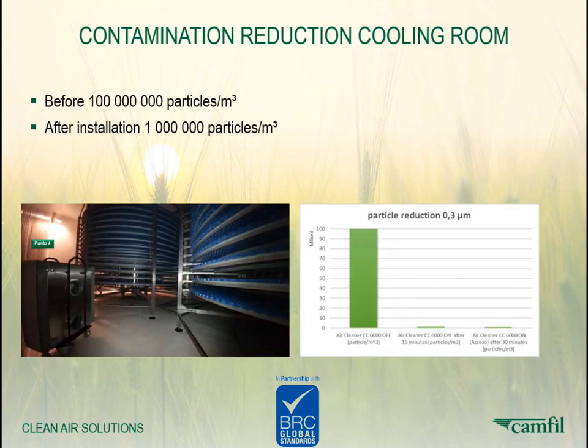With this slide, we'll describe the reduction of particles in the cooling room. In the staple diagram, you see the high green staple before installation with a concentration of 100 million particles per cubic meter at 0.3 micron size. Measurements after installation show only 1 million particles per cubic meter left. This means a reduction of 99% of the particles in the room and minimizes the risk of airborne contaminants getting in touch with the bread.